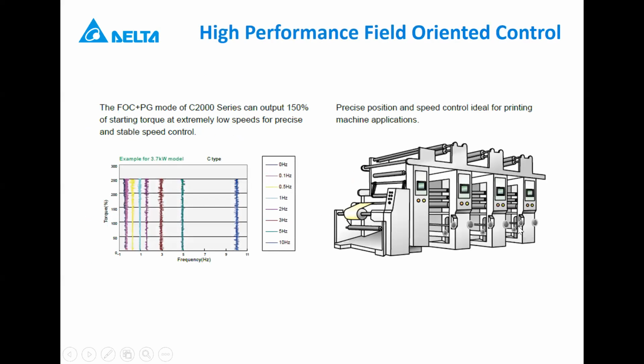These are some of the main key features I'd like you to remember about the C2000 drive. First, it's a high performance field oriented control. The field oriented control plus the PG mode, where you can add a PG card, can output 150% of starting torque, meaning you can overload it up to 150% of starting torque at extremely low speed for very precise and stable speed control. It can also do very precise positioning and speed control, which is ideal for printing machines.